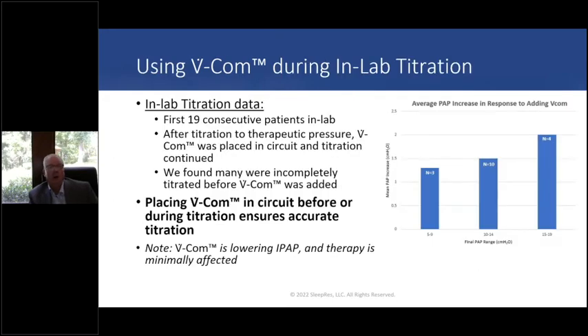Using VCOM in our lab during titration, the first 19 patients showed, as expected, that as you increase the pressure from 5 to 9, 10 to 14, 15 to 19, the pressure change required with the VCOM increases a little bit, because at higher pressures you have higher exhaust flow, and therefore more drop in pressure, more drop in EPAP. Of course the maximum was only about 2 out here.